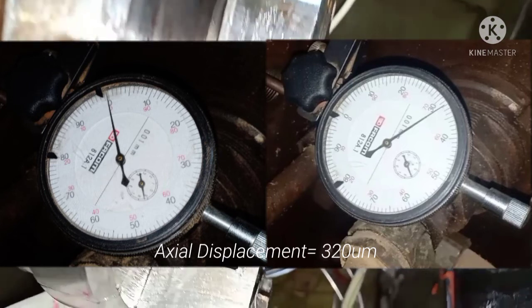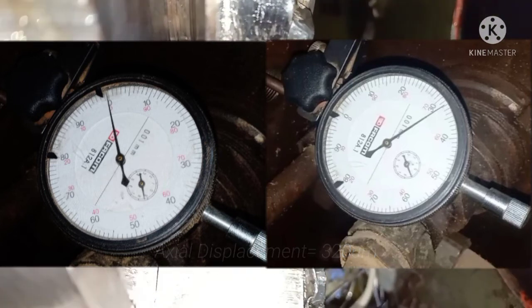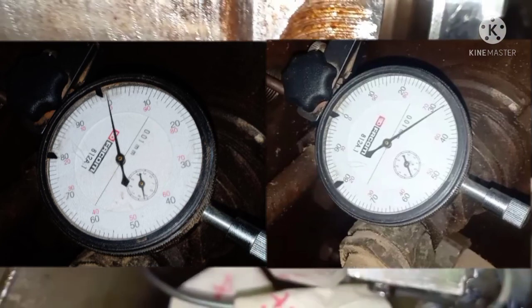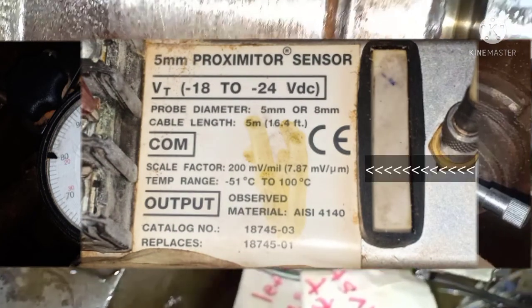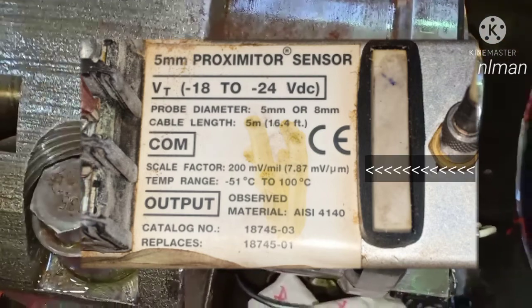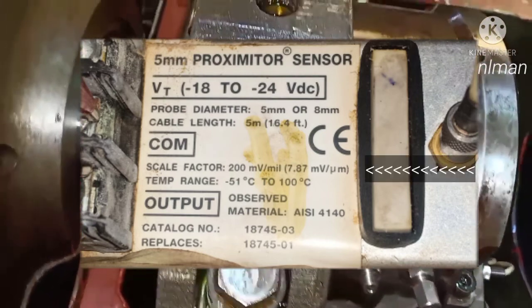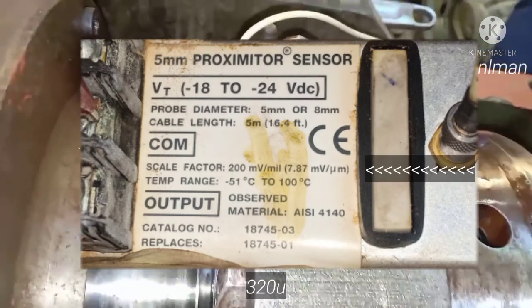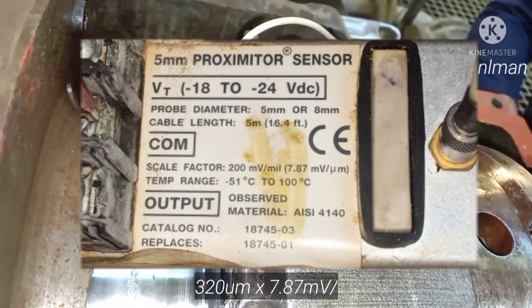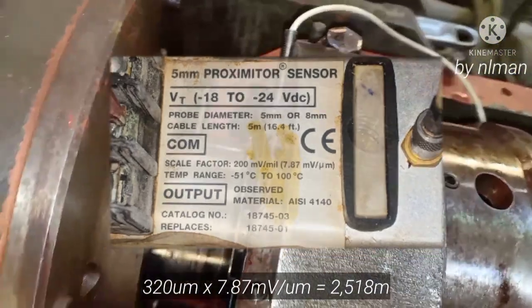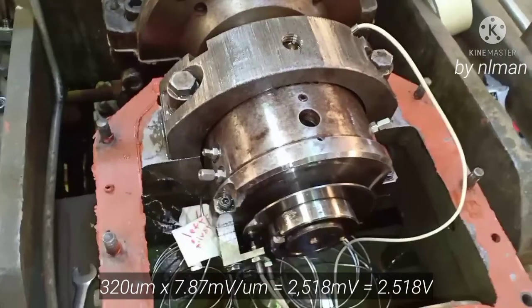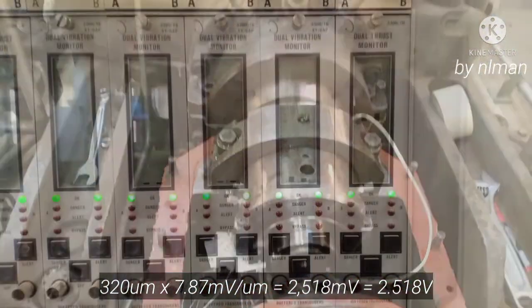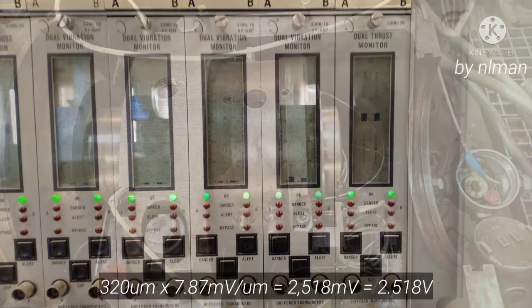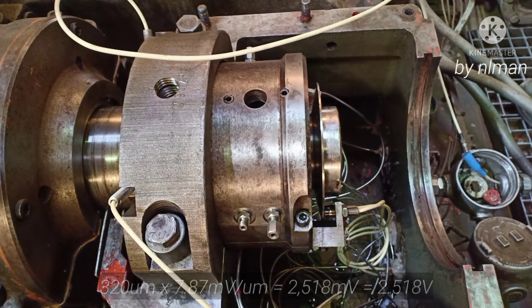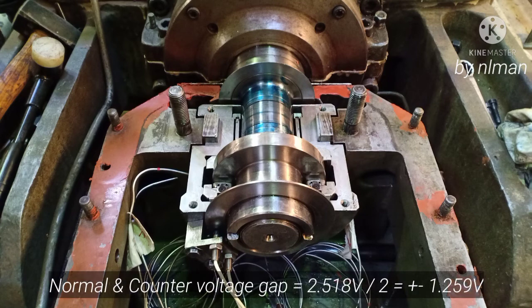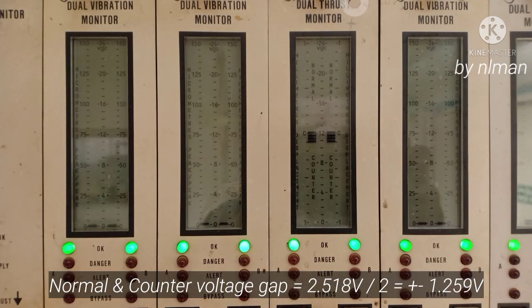So to compute the volts corresponding to this axial displacement, we need to multiply it by the scale factor of the proximity sensor of 7.87 millivolts per micrometer. Okay, so we will multiply 320 micron by 7.87 millivolts per micron, equivalent to 2518 millivolts, equivalent to 2.518 volts.